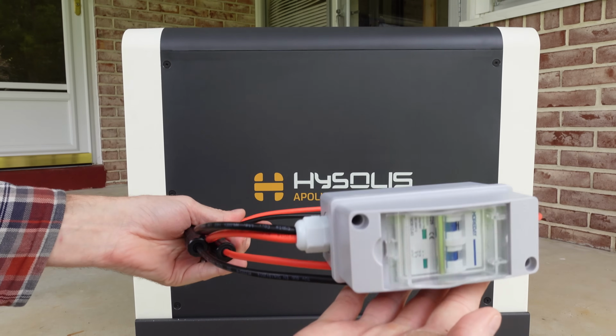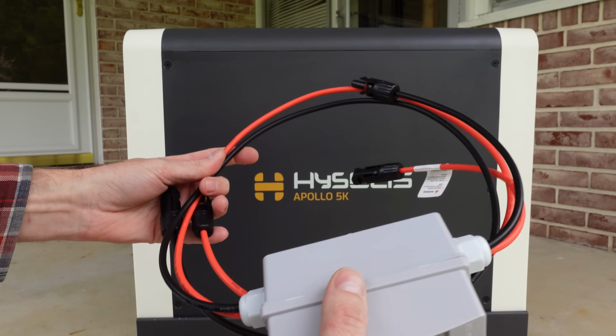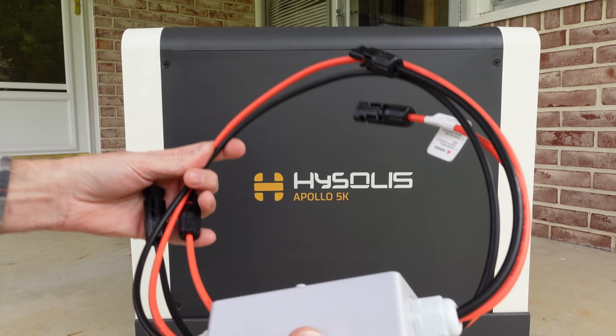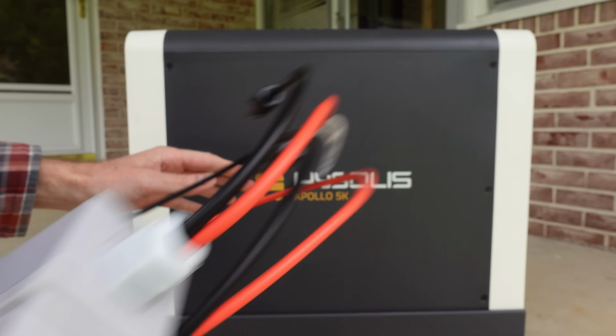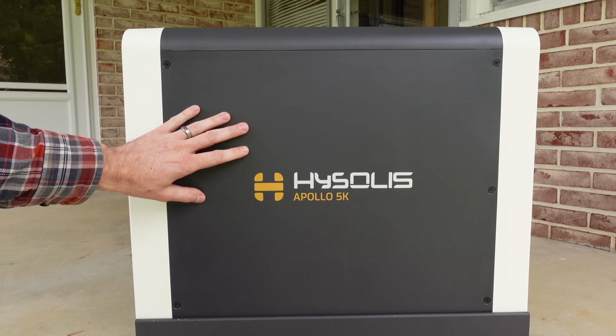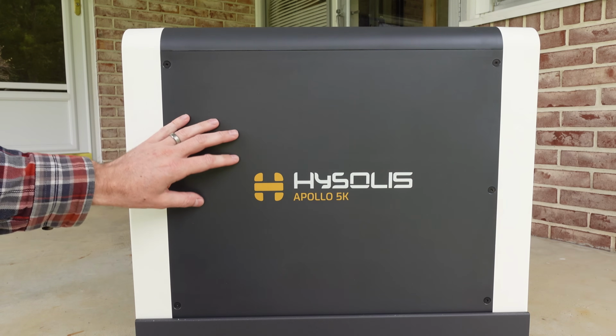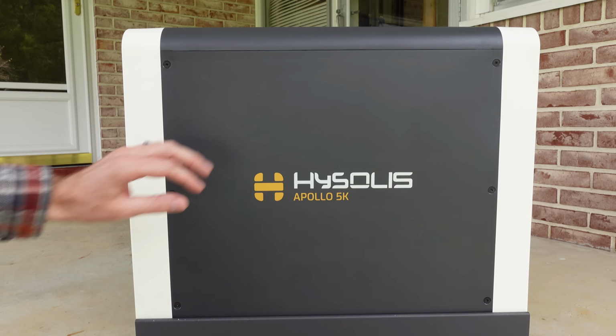We have a PV connection disconnect box, breaker, and cabling here. It's very, very cool to see that they provided this. Now, this power station can take up to 500 volts open circuit from your solar panels. That voltage is extremely dangerous if you were to come in contact with it.